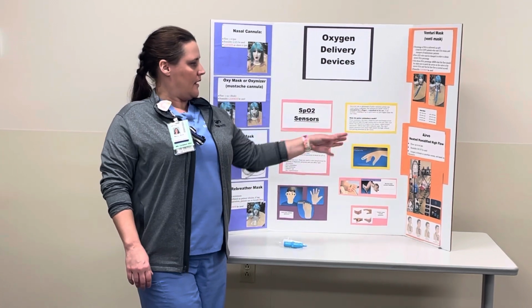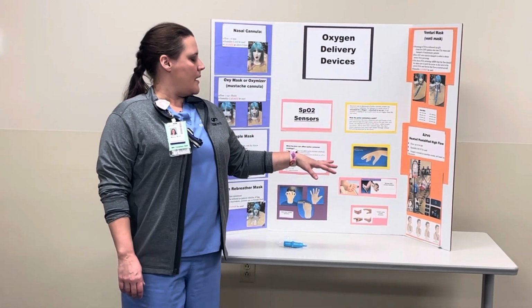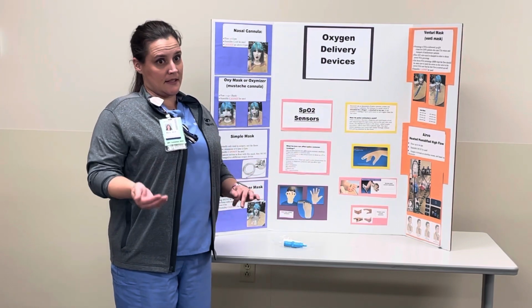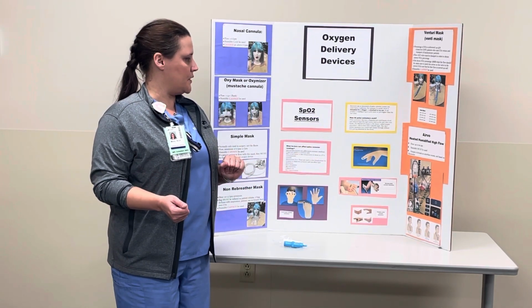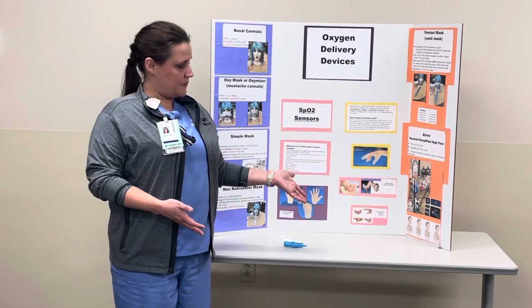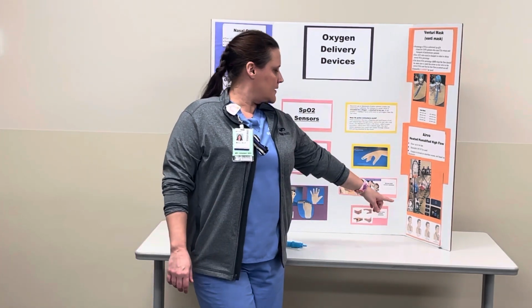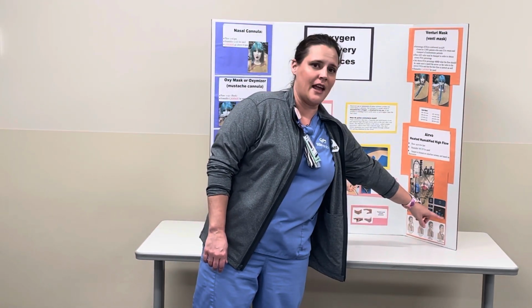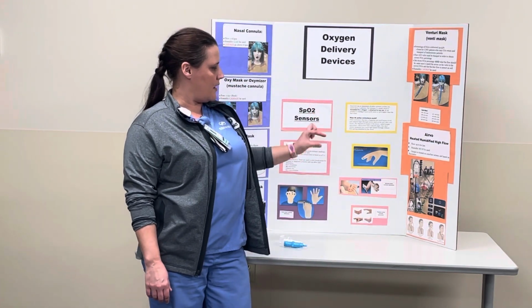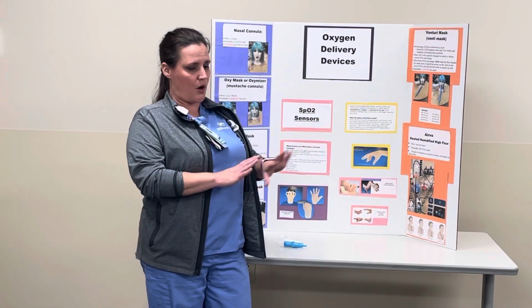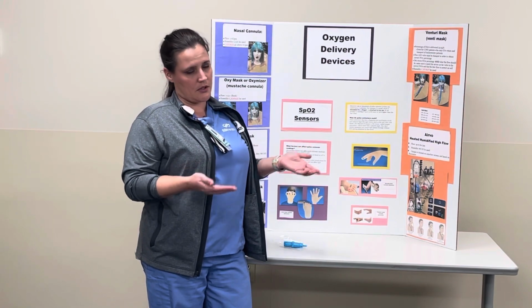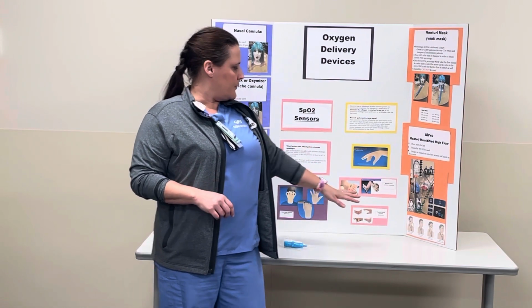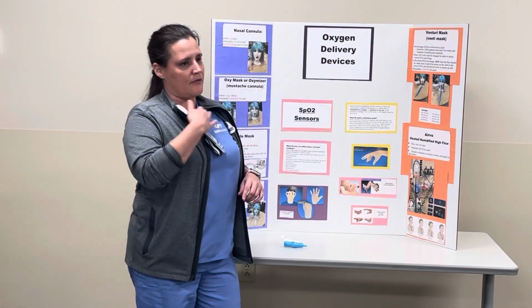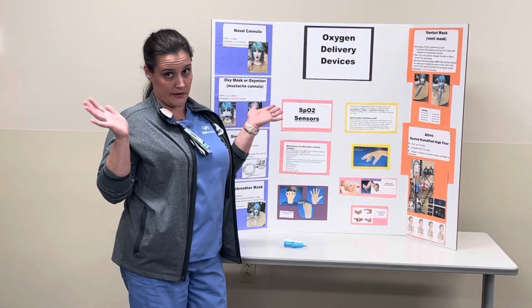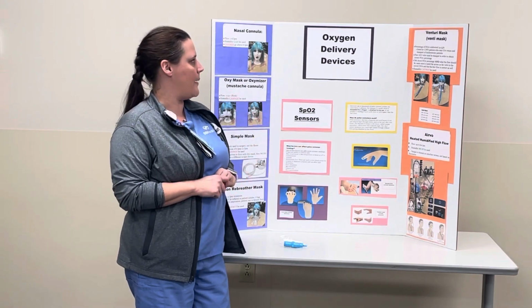Airvos are high flow heated humidity. They can go up to 60 liters per minute, up to 100% FiO2. Humidity obviously has to be used with this. When you titrate it, on the machine is a play button here. You push this play button, that lights up your screen, and then you turn the flow valve. The numbers on the flow don't matter. You use that to increase or decrease your FiO2. And there's different ways to do that: nasal cannula, we have mask options, and we have trach options. Again, respiratory is always there to help. We can help you no matter what. Just give us a call, we're happy to help.